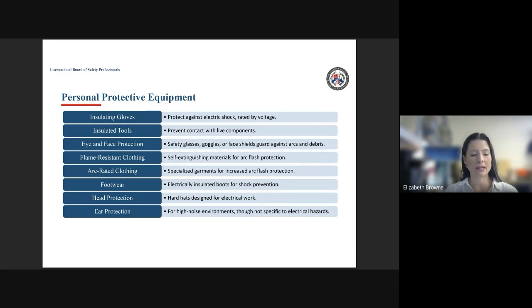But when qualified electrical workers are working with live electrical equipment, there is a requirement that they have the appropriate personal protective equipment as outlined by the NFPA 70E standards. The equipment is based on what level of hazard risk category or arc flash risk there is to the individual, and that is calculated based on a lot of calculations. There should be an arc flash study completed in your facility and there should be labels on equipment that would tell any individual what type of personal protective equipment they need to wear.